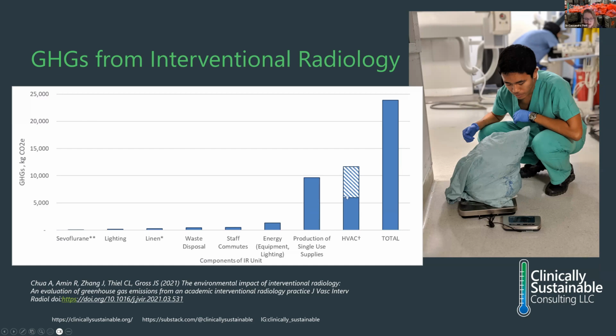HVAC was interesting because the hashed line represents the time when the operating rooms were actually not in use. About half of the HVAC-related emissions were coming from off-hours HVAC use. Basically, these ORs aren't needed for emergent cases. This operating room only worked 7 a.m. to 5 p.m., Monday through Friday, with no patients overnight or on weekends, but they still ran the ORs as if they were operating with patients.